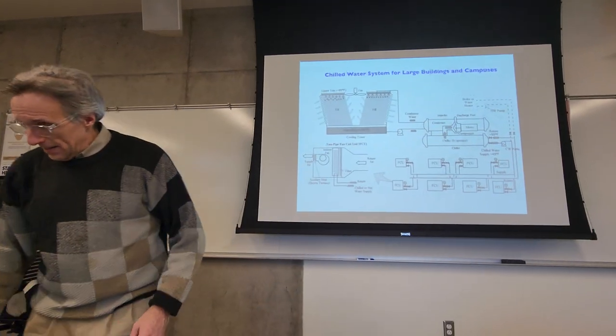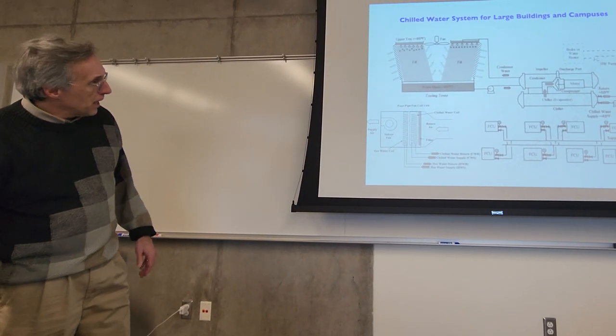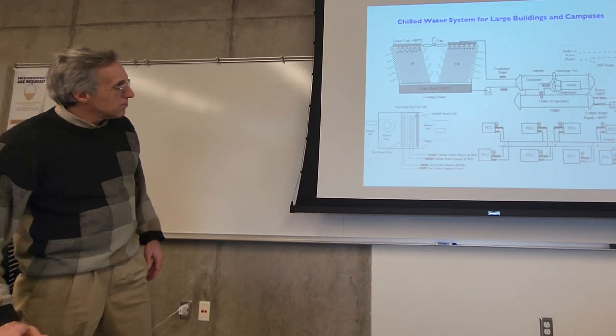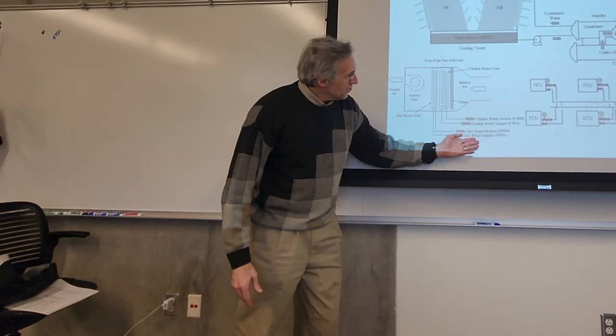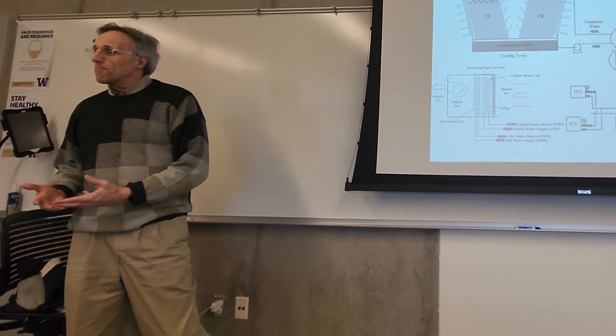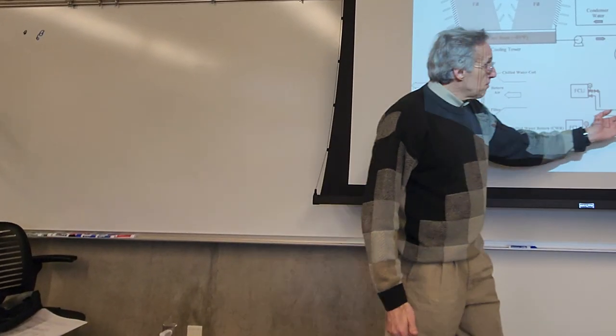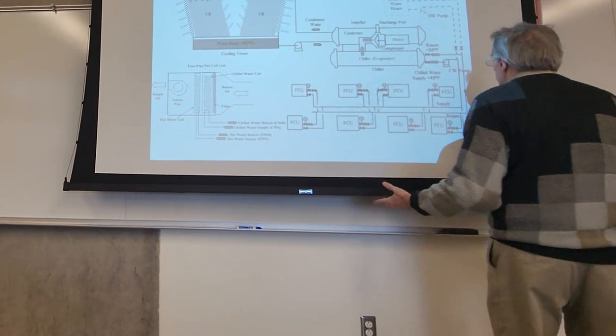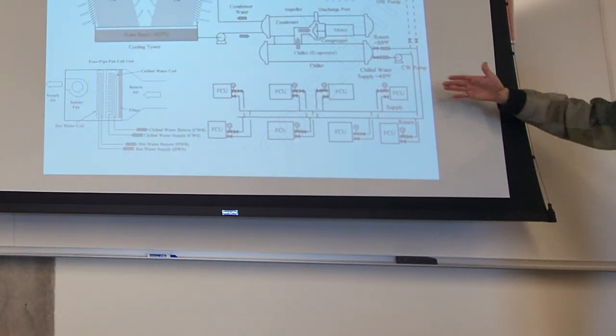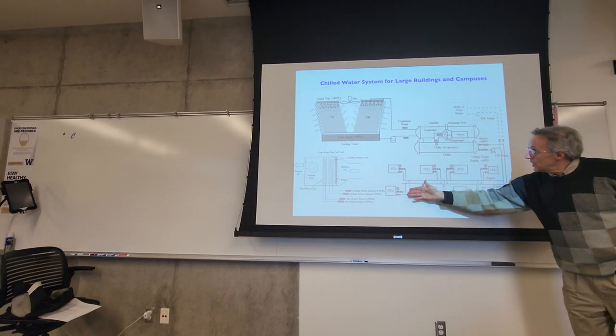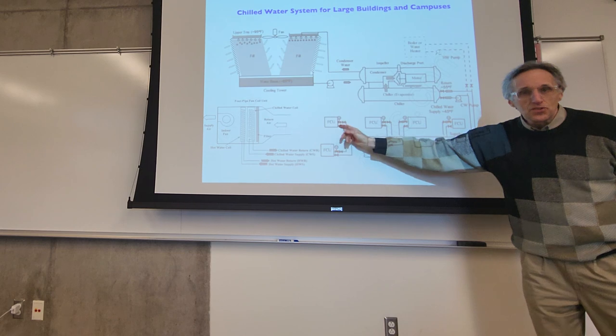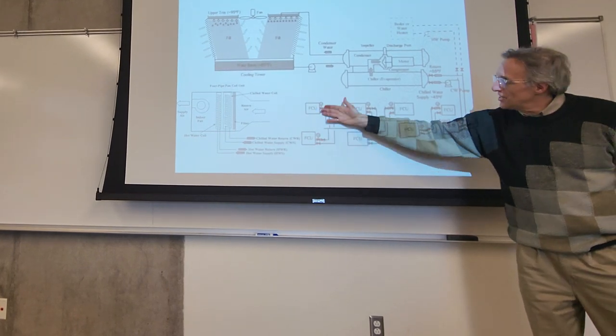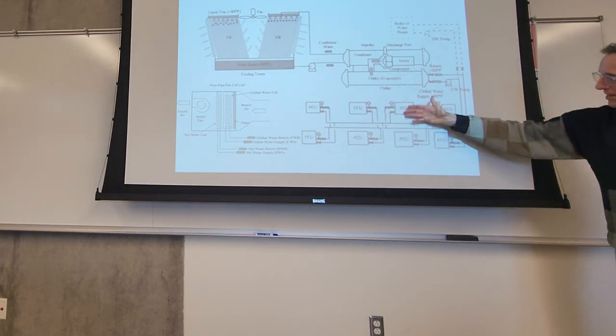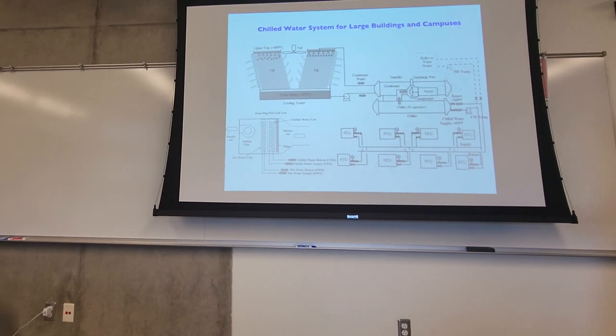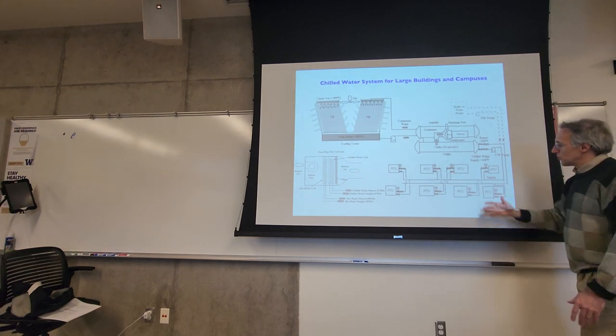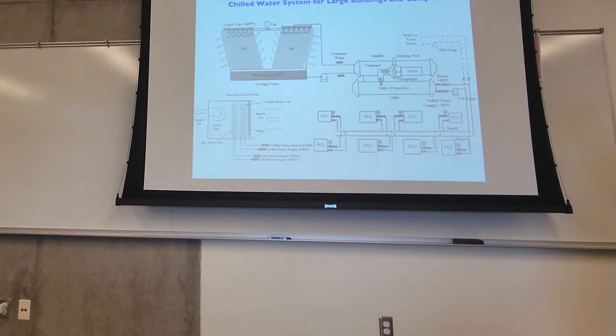And that's what we have. Actually, this is a four-pipe system. That's the two-pipe fan coil unit, and then the four-pipe fan coil showing the connections to the hot water supply. Now, these systems can be elaborate, and it can be difficult to design the piping system, because your intuition would suggest if you're serving a whole bunch of different locations with a single pump, by the time you get out to the end, there's not going to be a lot of pressure left. And these folks down here are going to get starved with water, and these folks are going to get blasted with water. And there's actually little tricks you can employ in your design to balance things out. So pressure is roughly constant in each of the fan coil units.